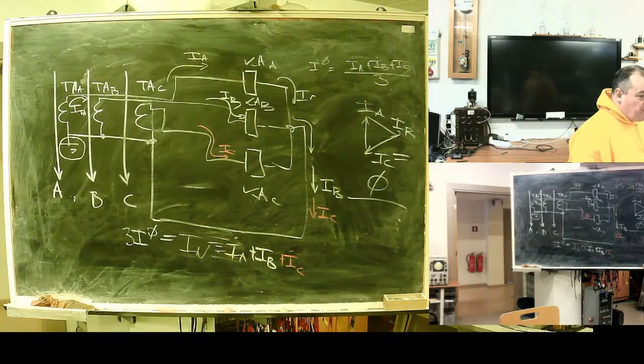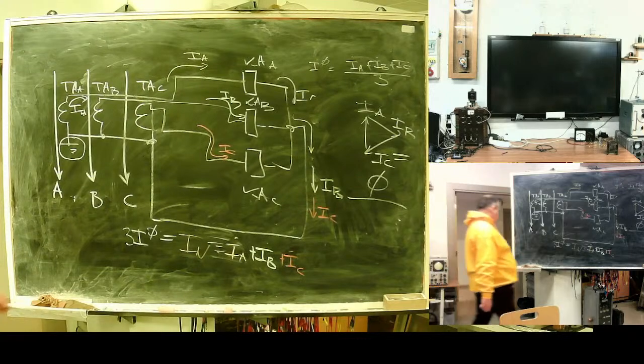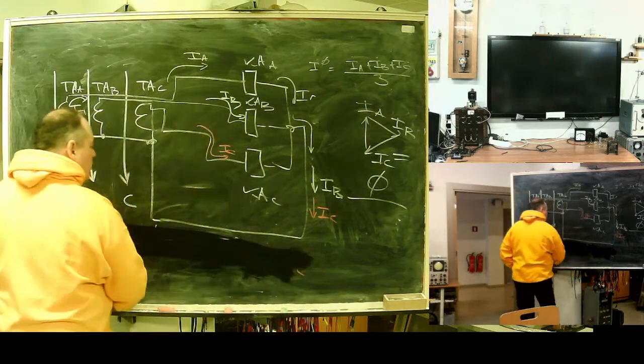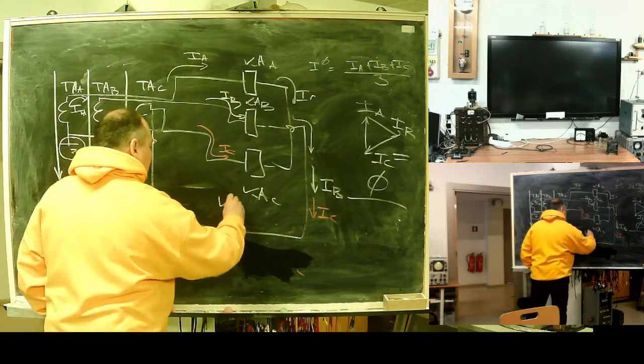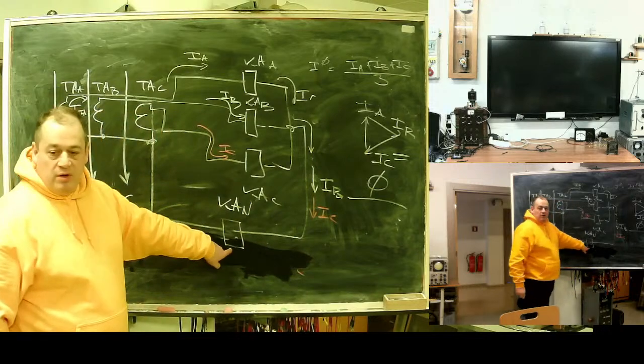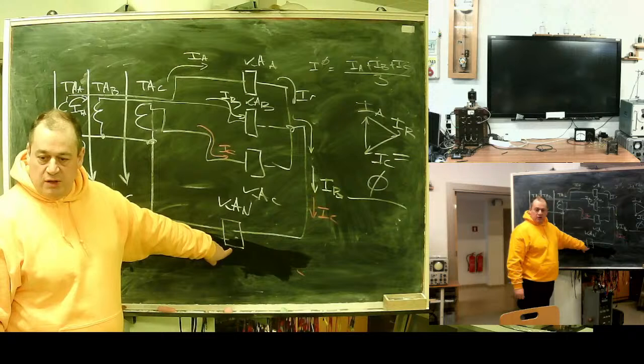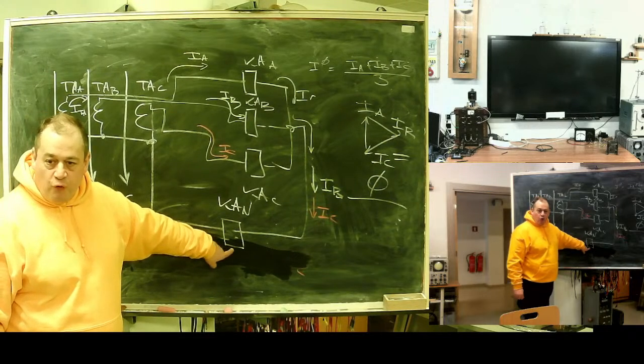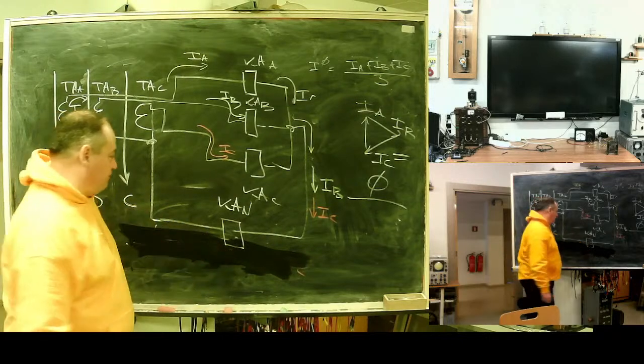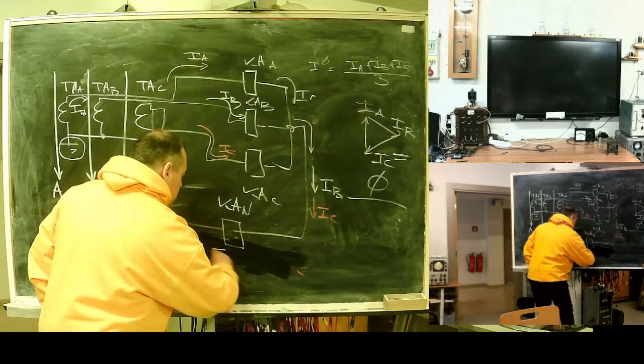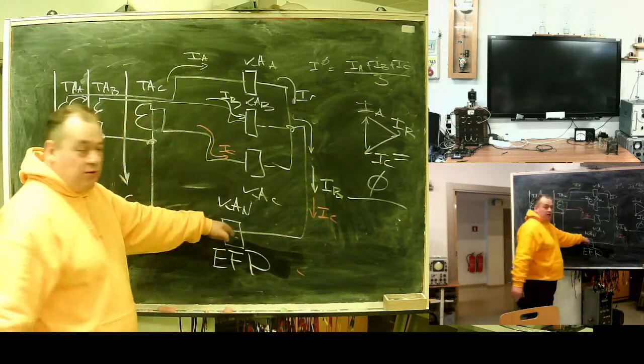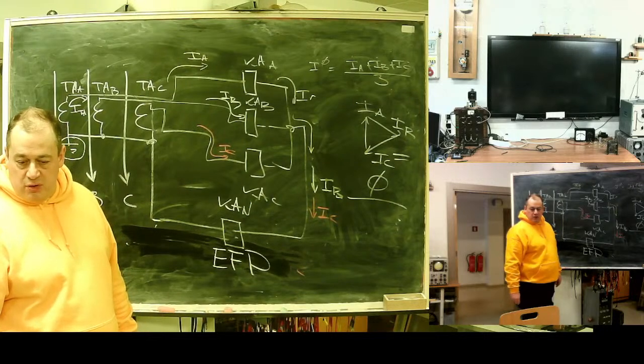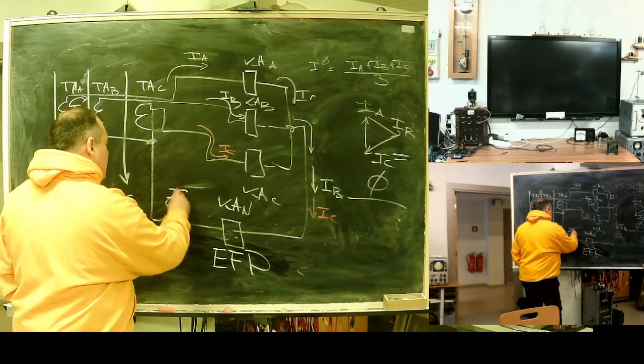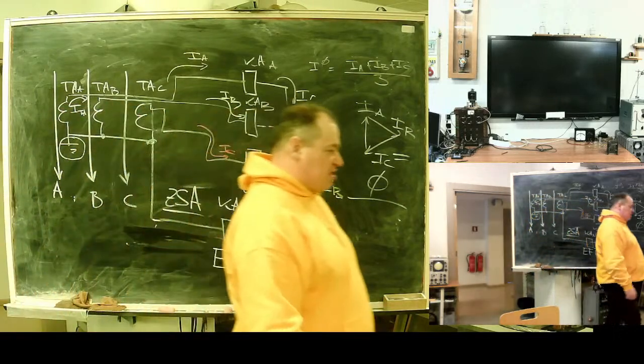In case of Earth's fault, what will be zero sequence current? Full current of fault. Plant a relay here, and it will have, in theory, 0 in signal in normal regime and full current of fault in case of Earth's fault. Earth's fault protection. This relay is very good for Earth's fault protection. ZSA, zemesslēguma aizsardzība.